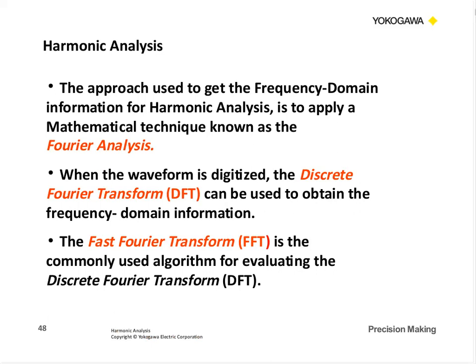When the waveform's digitized, we get a basic discrete Fourier transform, what they call a DFT. And then in our instruments, we use the fast Fourier transform, the FFT, to get the harmonic data. You get a quick display, it's accurate. You can use the discrete Fourier transform in some instruments. It's a little bit slower and will give the results a little bit different, but in our instruments, we use the FFT.